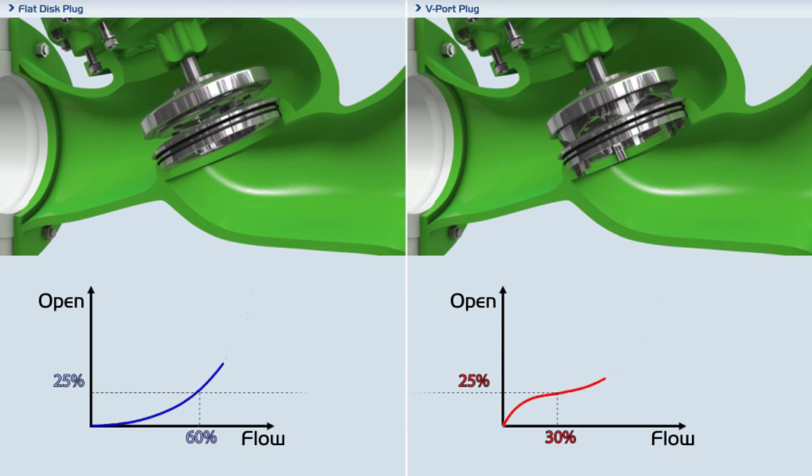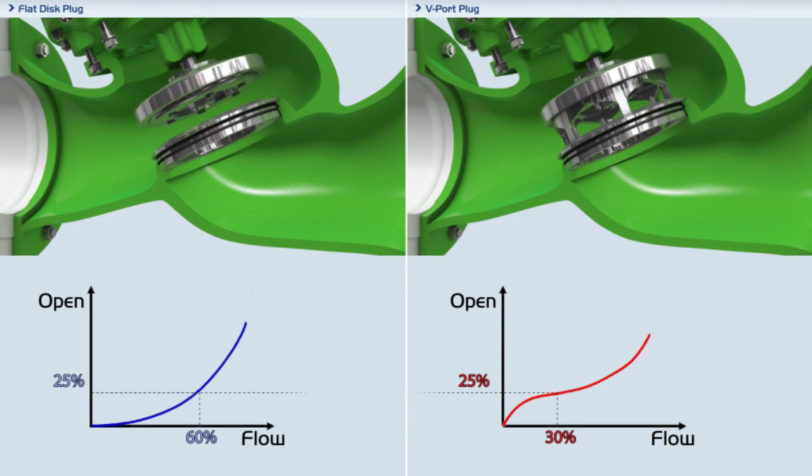The V-port allows a very wide flow range with relatively high pressure reduction and may save the installation of a secondary, smaller bypass valve needed for low flow.